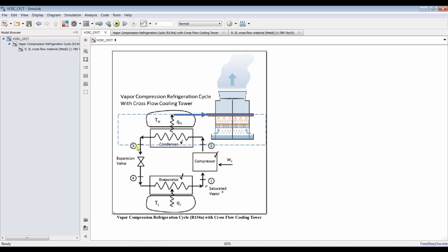So what is new is that you are going to utilize a cooling tower for the condenser unit cycle as a heat rejection. This is high temperature and this is low temperature. This is the cooling tower. So it's better to use a wide range of different operating conditions via a cross flow cooling tower. So I do recommend to attach a cross flow cooling tower. We can attach different types of cooling towers if you would like, but this is just an example.